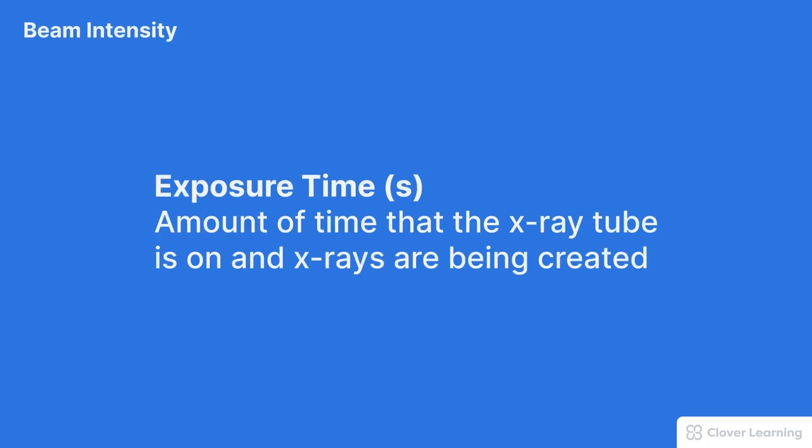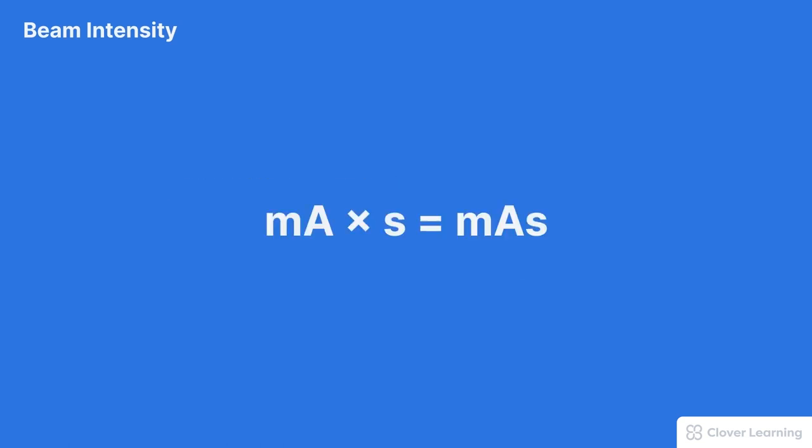The MA has important relationships with other exposure factors, especially exposure time. The exposure time refers to the amount of time that the x-ray tube is on and x-rays are being created. The product of the MA and exposure time in seconds is called the mAs. The mAs is an important factor influencing the intensity, that's the quantity, of the x-ray beam. Usually an operator sets the mAs rather than setting the MA and time separately.